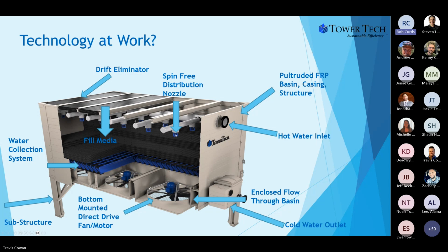We were able to develop a way that as the water flows through, we spin the water in a disc that we have in that large 2-inch opening, and now it sprays the water out, but it has self-cleaning action. So by getting the self-cleaning action, you don't have to put people up on top of the cooling tower to always have to go on top and get exposed to cleaning the nozzles out on a regular basis.